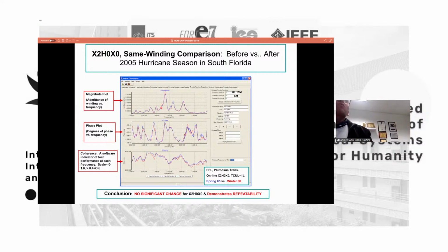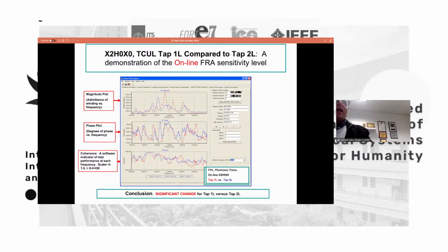They plotted it twice in two different weeks and found that this phase is healthy. This one here is the angle, from minus 90 to plus 90, and this one is the coherence or correlation coefficient. They also changed the tap changer, remember, the online tap changer, to change the turns ratio. They measured on tap 1 and tap 2 and found that yes, it can detect changes in the turns ratio.